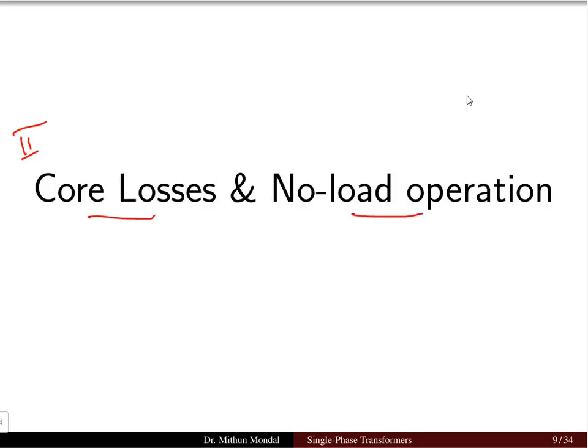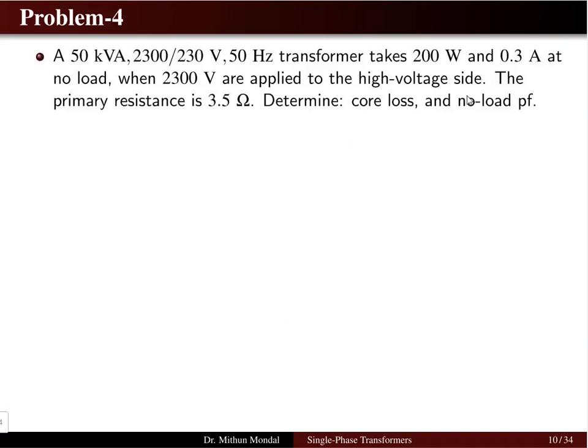So here we will not include anything on the copper loss. We will take only core losses into account, and the transformer will be under no load operation. So the 50 kVA, 2300 by 230 volt, 50 hertz transformer is taking 200 watt at 0.3 amps at no load. So there is no load on the transformer and the power is 200 watt. This is the input power of the transformer.